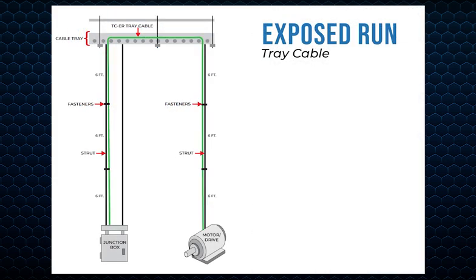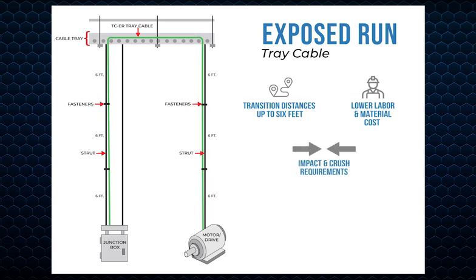In order to transition tray cable freely between cable tray and utilization equipment or devices, it must have another designation per the NEC. Cables with the TCER, or Tray Cable Exposed Run rating, are permitted to transition distances up to 6 feet without continuous support. The use of TCER rated tray cable will lower labor and material costs over typical installation methods. TCER complies with impact and crush requirements of Type MC armored cable, and NEC Article 336.10 uses are permitted. Per NEC, grounding for utilization equipment or devices must be provided via the conductor within the cable.